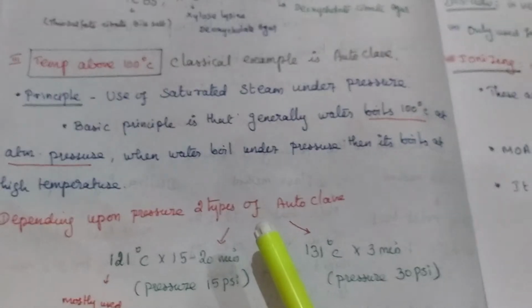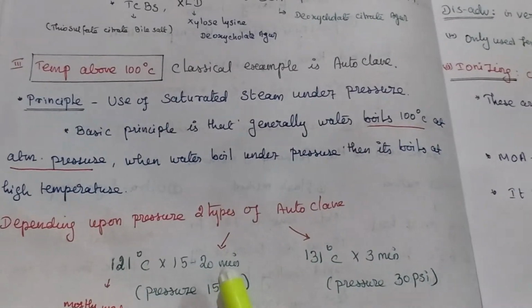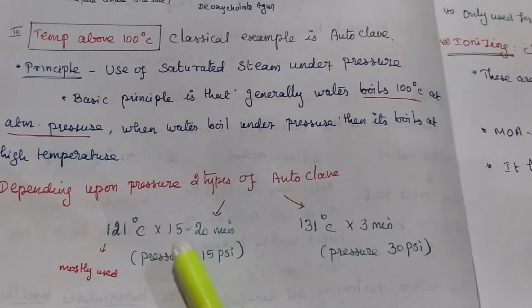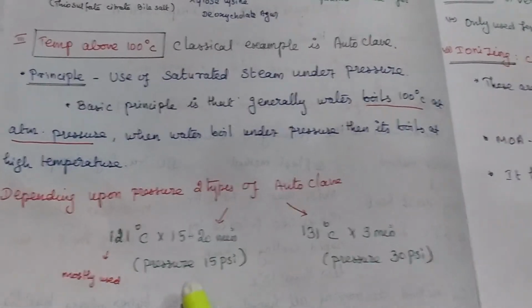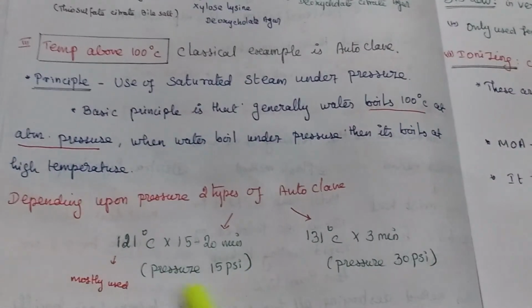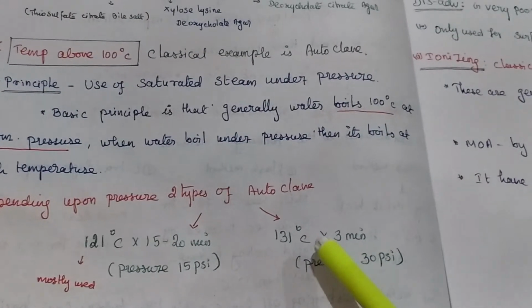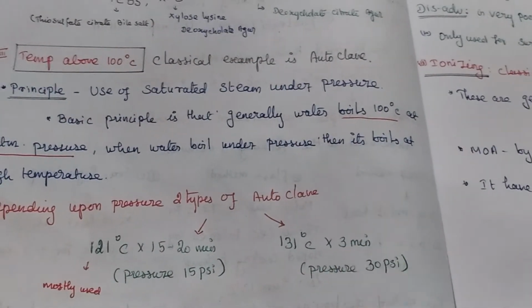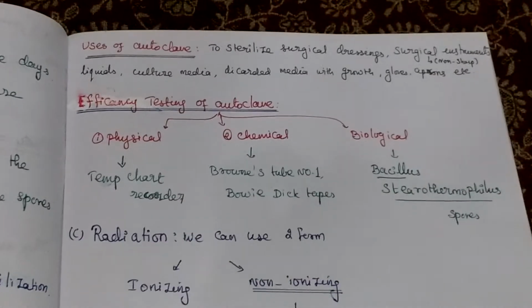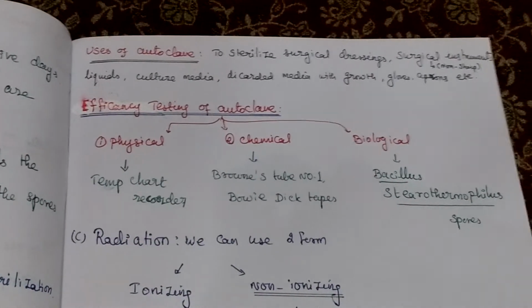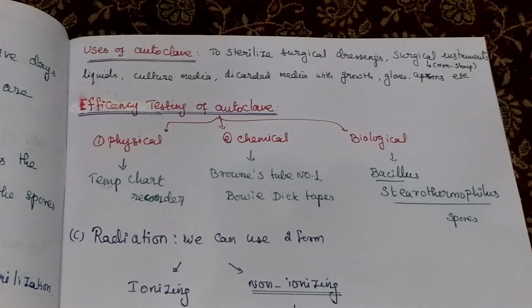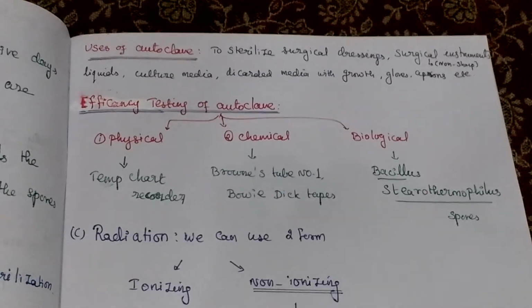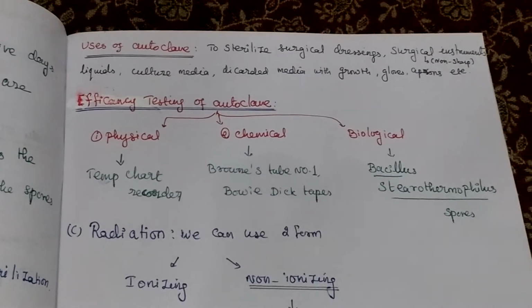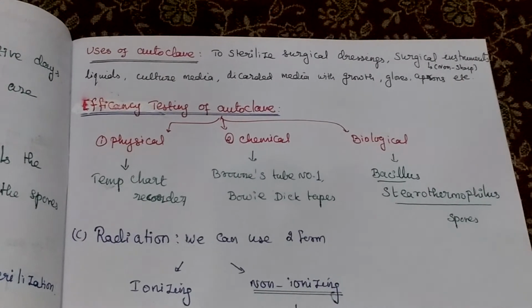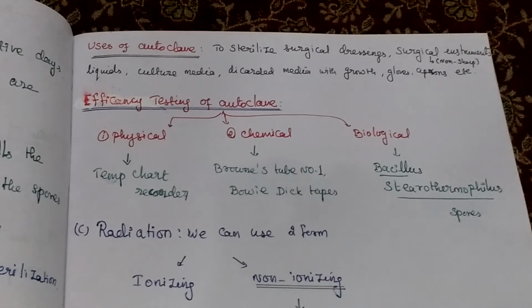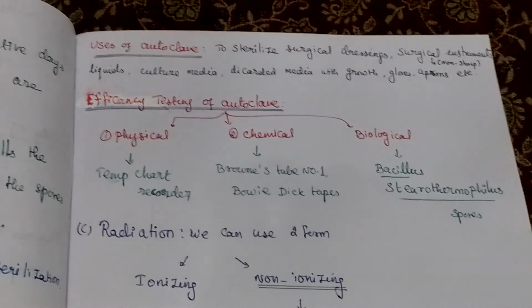Depending upon the pressure, there are two types of autoclave. First one is 121 degrees Celsius for 15 to 20 minutes, pressure 15 psi. This is the most used method. Second one is 131 degrees Celsius for 3 minutes. Then uses of the autoclave: to sterilize surgical dressings, surgical instruments, especially non-sharp material, liquids, culture media, discarded media with growth, gloves, aprons, etc.